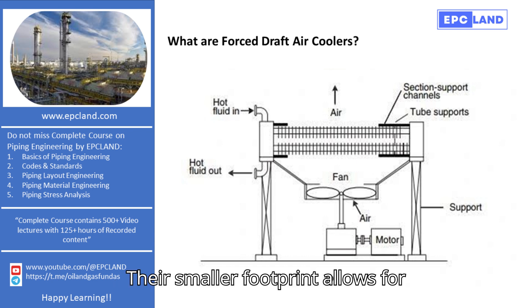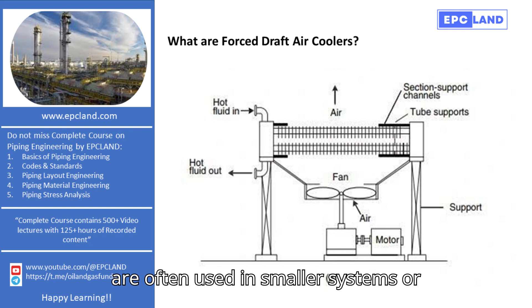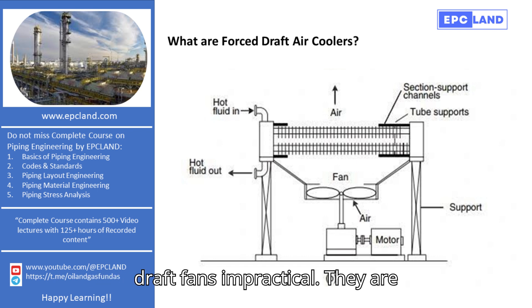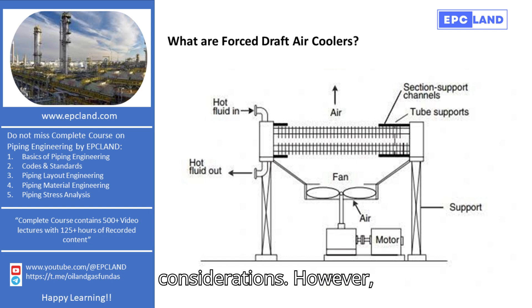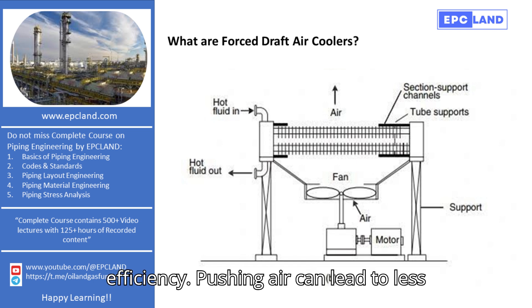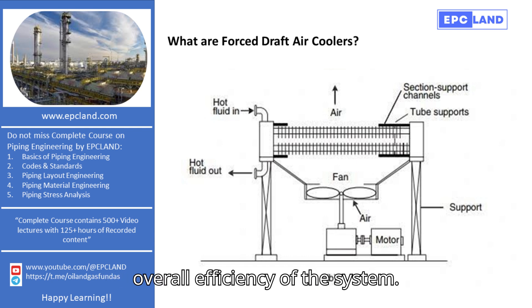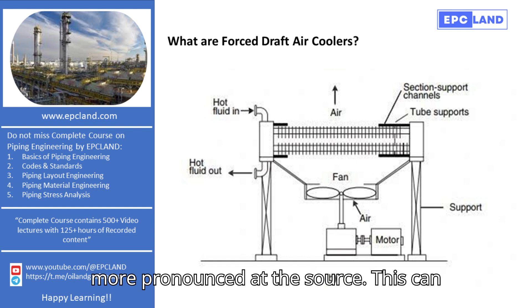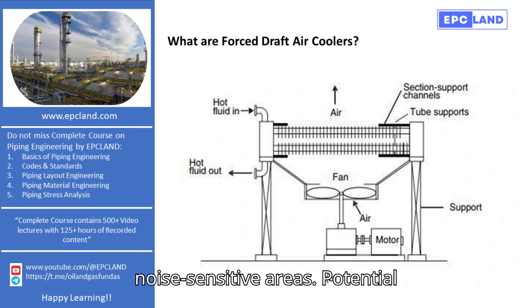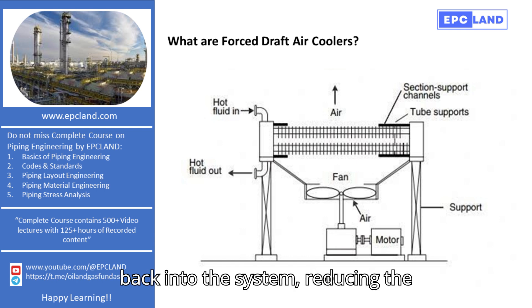Their smaller footprint allows for greater flexibility in system design. Effective for smaller systems — these fans are often used in smaller systems or where the ductwork design makes induced draft fans impractical. They are ideal for situations where simplicity and cost-effectiveness are key. However, forced draft fans also have disadvantages: lower efficiency — pushing air can lead to less uniform airflow and increased recirculation, reducing overall system efficiency. Higher noise levels — since the fans are at the intake end, noise can be more pronounced at the source, which can be a concern in noise-sensitive areas. Potential for recirculation — in some designs, forced draft fans can cause air to circulate back into the system, reducing the effectiveness of ventilation or cooling.